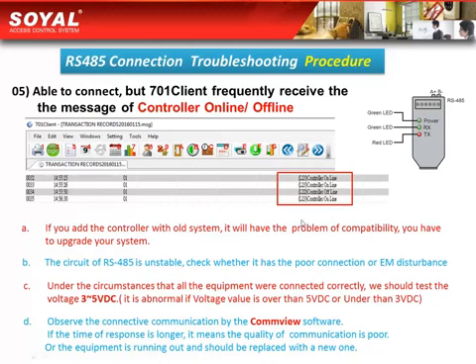In this situation, you can see the status sometimes shows online and sometimes shows offline. At this time, there are four possible reasons. First, if you have added a controller with an old system, the system may be too old and there will be a compatibility problem — you will need to upgrade your system. Second, the RS485 circuit is unstable; for example, there may be a poor connection or electromagnetic disturbance.